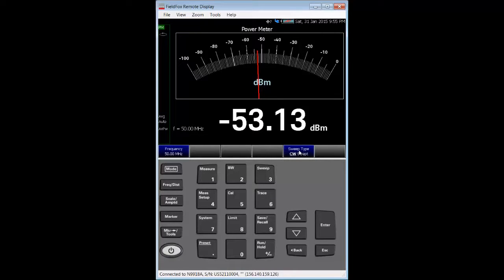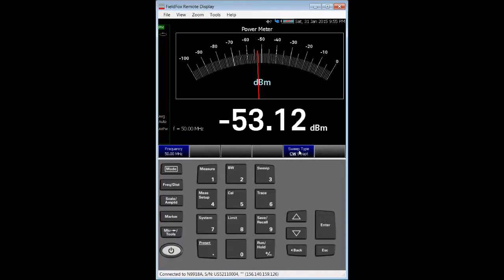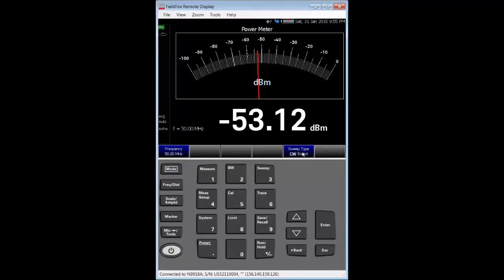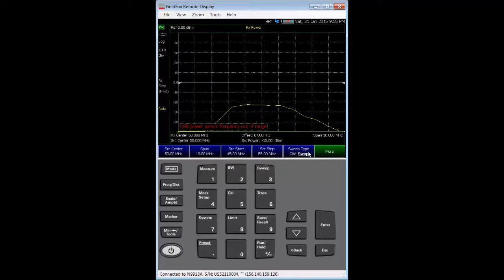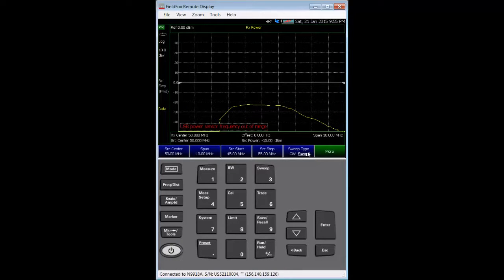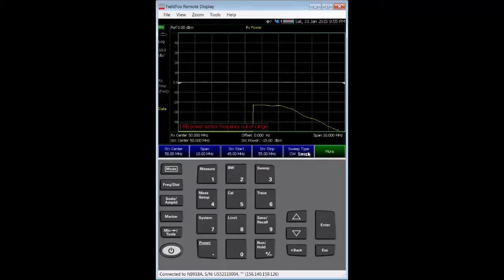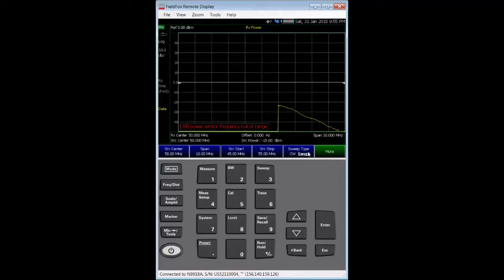Now, we'll get into setting up the instrument to measure the device's conversion loss. Notice that the power meter mode defaults to a CW measurement. We look for the sweep type soft key, and then we set it from CW to swept. For the moment, ignore the error message, as we still need to make settings that will work for our U2002A power sensor.